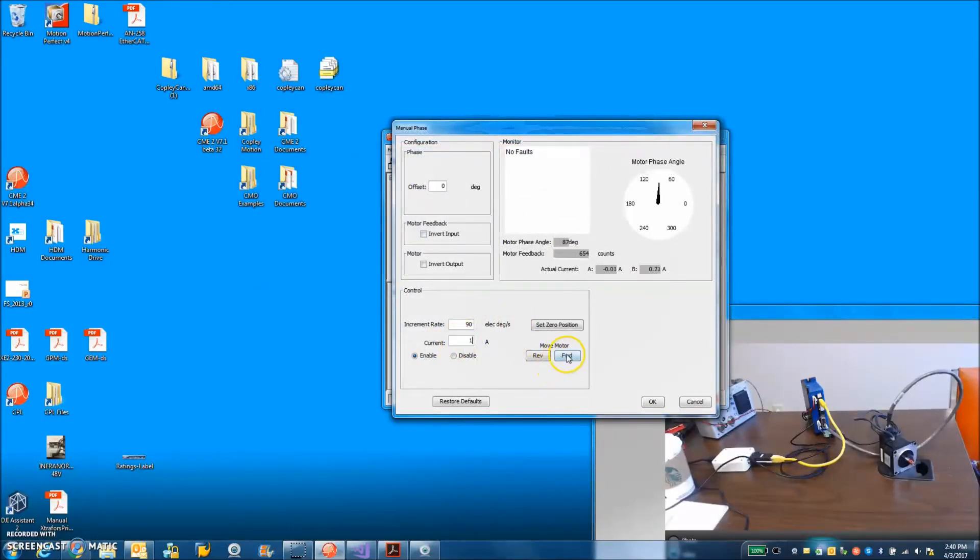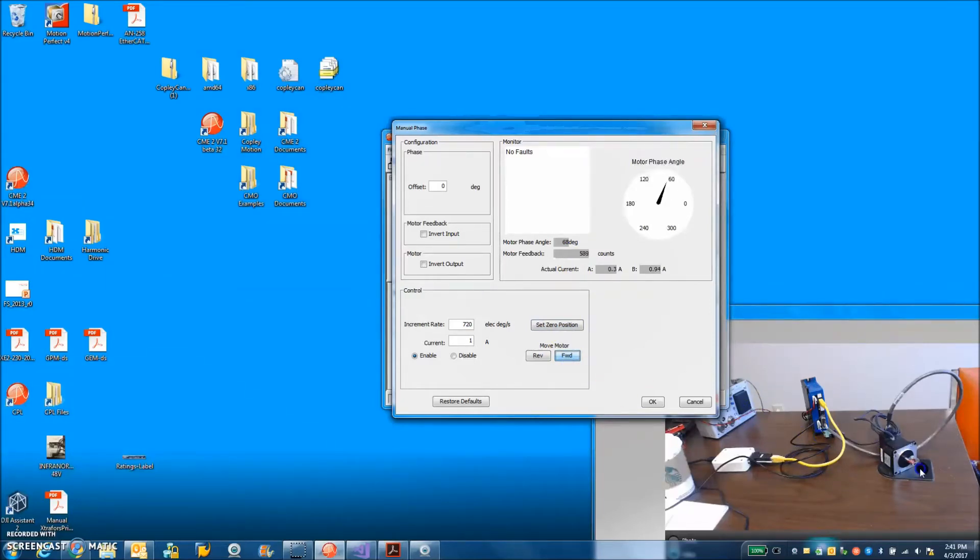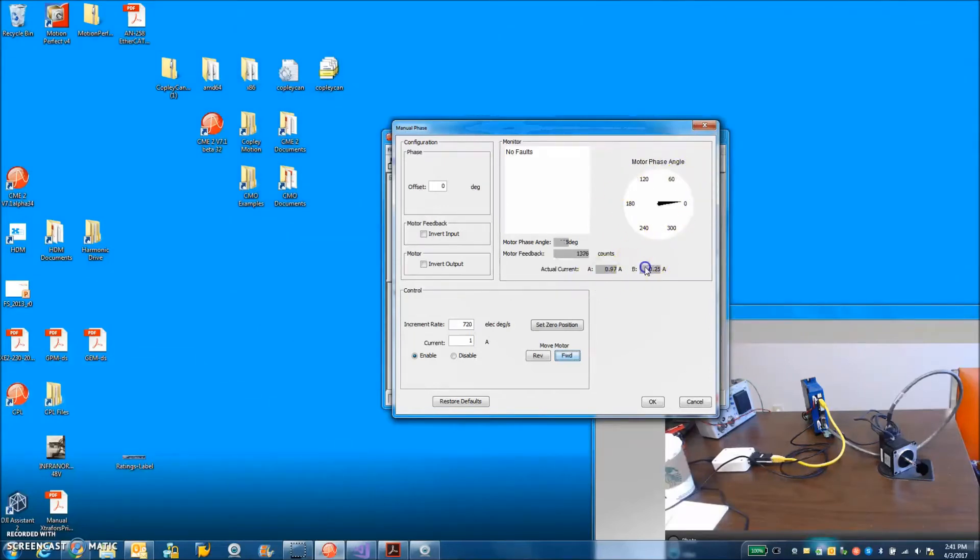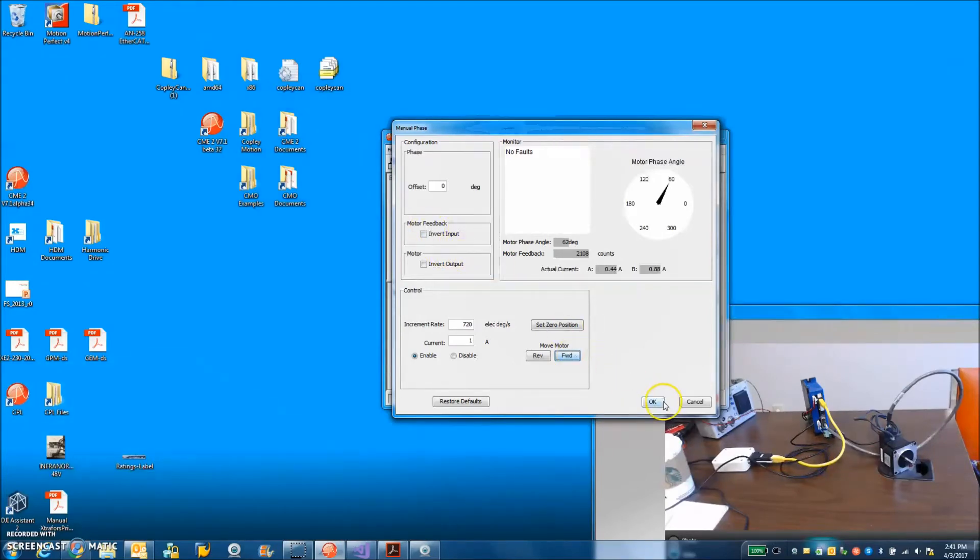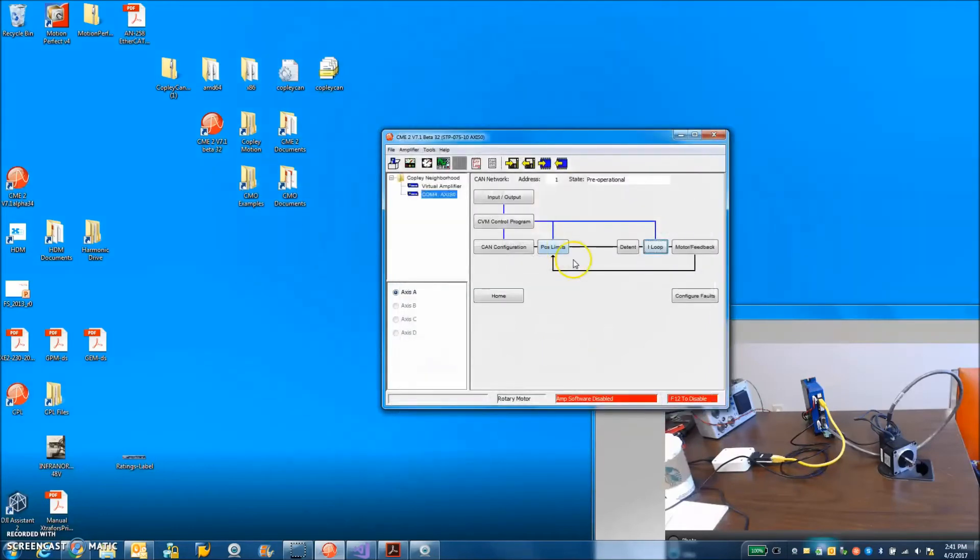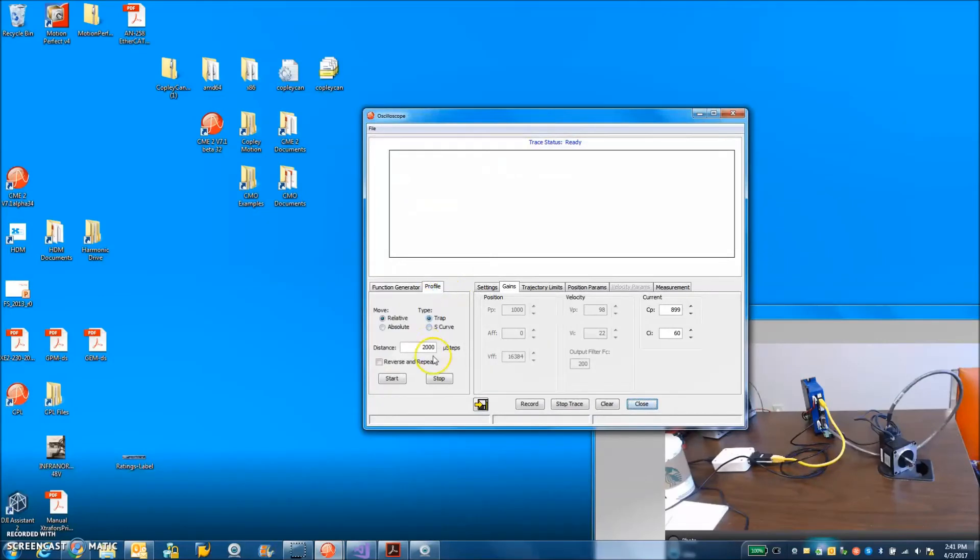So tools manual phase. We can give it an amp. Forward rotating. That's a little slow to see it turning on the screen here but as you go forward counts go up. So check that out. I got clockwise of my motor here going forward and as I rotate the current vector everybody gets a turn to deliver current plus or minus an amp and my counts go forward. There's about a half a rev. So yeah I got a 4000 count. Check that out. And forward positive counts. I don't need to invert the motor or feedback. So we're good with that.